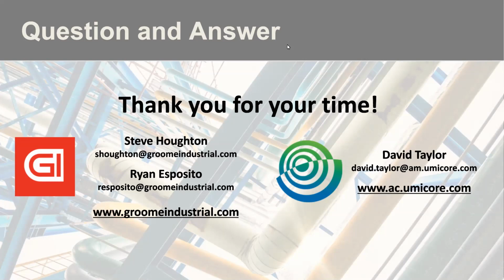Yeah, another thing. Sorry, I'm going to say it all depends a lot, but it depends on what catalyst is in there, the depth of the catalyst. Typically natural gas units, they just deactivate slowly. It's more of a thermal deactivation, whether it's our catalyst or Cormetech's catalyst. We could look at the design of what's in there and kind of give an idea, but if you do know your ammonia slip and your current DeNOx, that should give you at least some indication of what your lifespan is left from the original design, what was quoted to you.